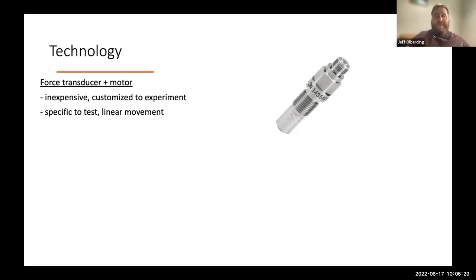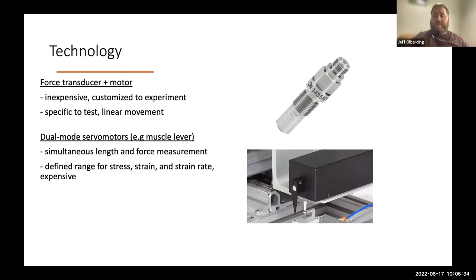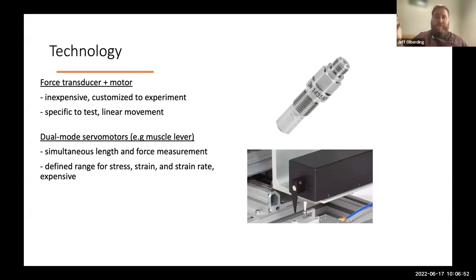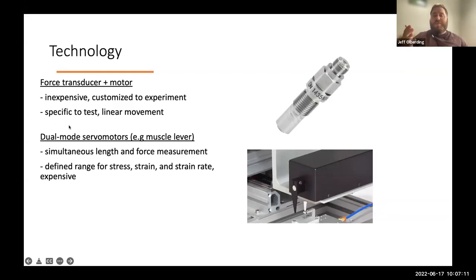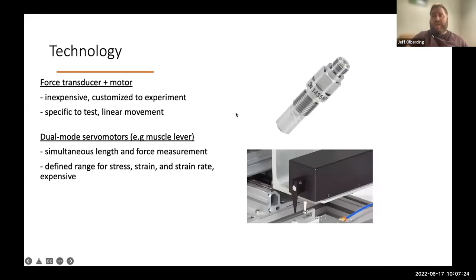If you're in a biology department with a muscle physiologist, you may have a dual mode servo motor sitting around. These are commonly called muscle levers and they have the advantage of simultaneously controlling and measuring force and changes in length. Some of the disadvantages are that this type of instrument is relatively expensive. They also have a defined range for both the forces and strains they can apply, as well as strain rate. If you're looking at a viscoelastic material, the material properties will be dependent on strain rate, and that may be limited by the range of outputs of the motor itself.